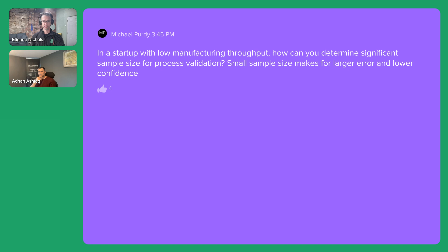Right, okay. So in a startup with low manufacturing throughput, how can you determine significant sample size for process validation? Small sample size makes for large error. Yeah, okay. So that's a really good question. Typically, you can use sampling plans. And I know maybe you've already used sampling plans, and this may not be the answer that you're looking for. Well, things like ISO 2859 and 3951, you've got sampling plans depending on the size of the sample, and it does account for low volumes, and that's really where you have to look at possibility of 100% verification, and validation may not be the solution.